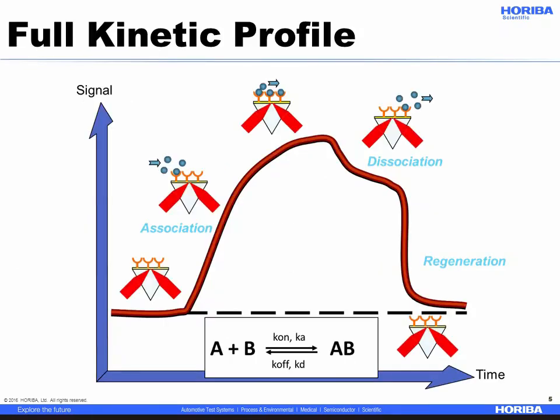Here is an example of the kinetic curve. The initial step is to functionalize the ligands on the surface of the chip, and then you inject your sample, and as analyte bind to your surface over time, you will observe a change in the reflected light intensity. There is a satisfactory linear relationship found between signal change and mass concentration of analyte. The SPRI signal, expressed in resonance units, is therefore a measure of mass concentration at the sensor chip surface. This means that the analyte and ligand association and dissociation can be observed and ultimately rate constants as well as equilibrium constants can be calculated.